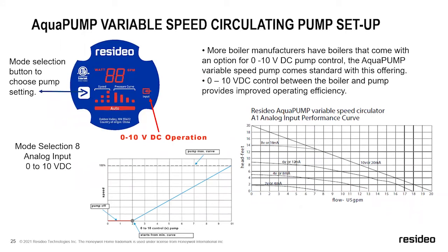And I wanted to touch on our variable speed output. I'm seeing more and more boilers that are starting to provide variable speed output signals, and it makes complete sense to me. There's a couple of brands, I think IBC, Lochinvar. I don't stay up with all the boiler brands, but they're creating variable speed outputs. I'm a big fan of using that because, as I had mentioned in the previous hydraulic separator examples, that pump, if you're using fixed speed, is designed for maintaining proper temperature differential with the boiler on maximum firing rate.